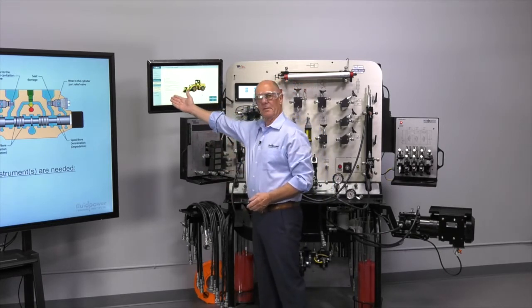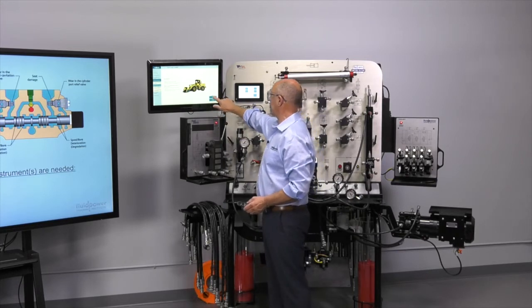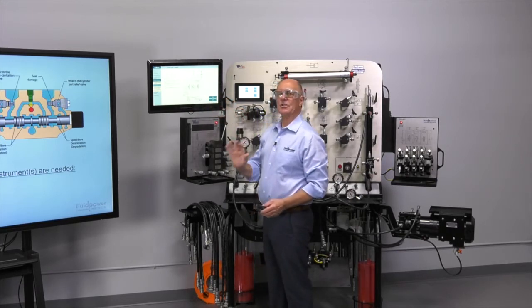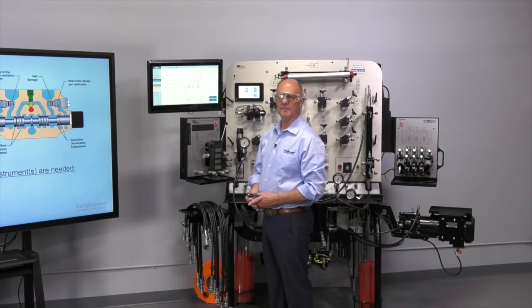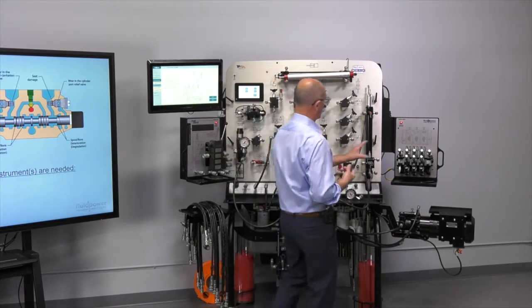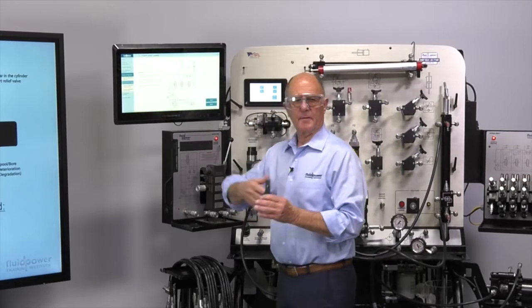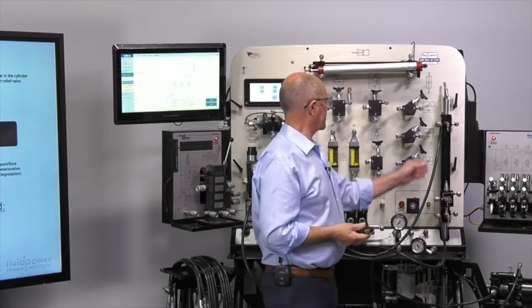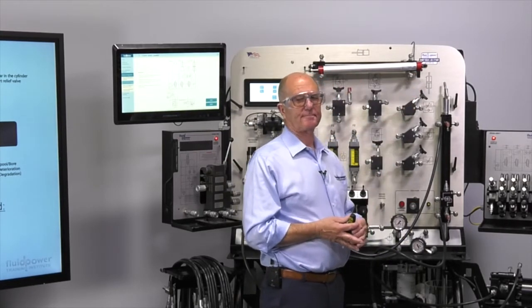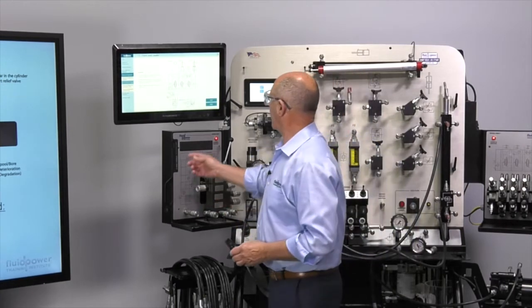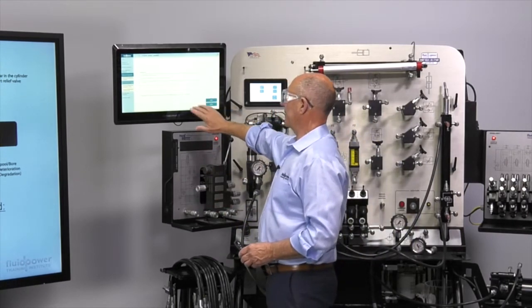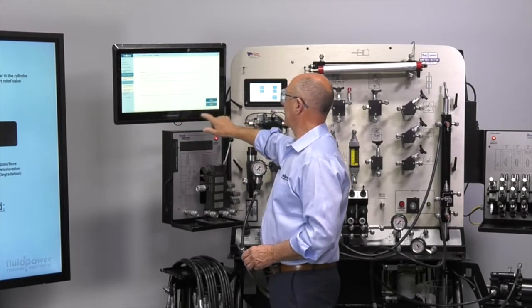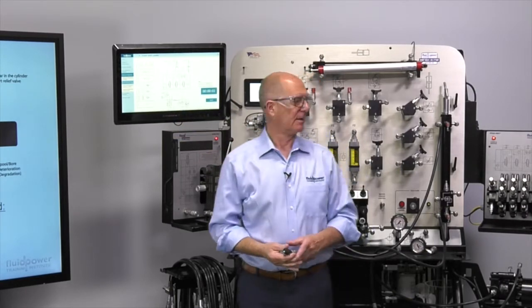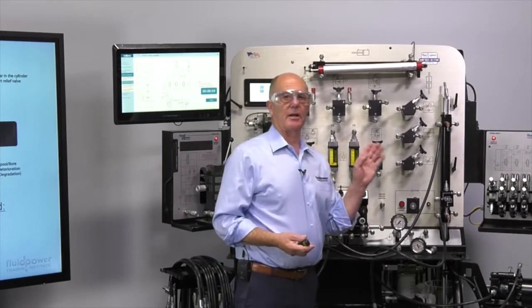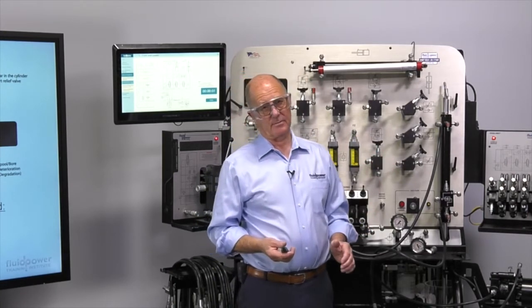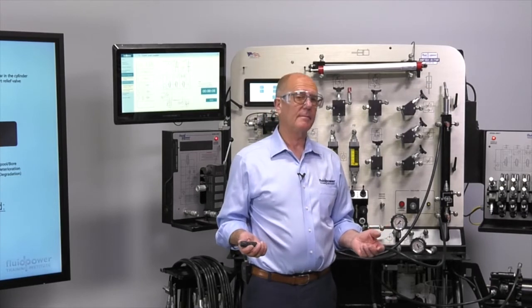It tells me what the problem is, what the operator's complaining about. I go to the next screen. I build the exact circuit that you'd find on this front-end loader. So you build it with this valve. When the student finishes all the setups and raises the load, it'll hold position. However, when the student goes to the next screen, there'll be some instructions, and then it'll auto-fault, meaning that the next time the student raises that cylinder, it's going to have a vertical downdrift in real time.